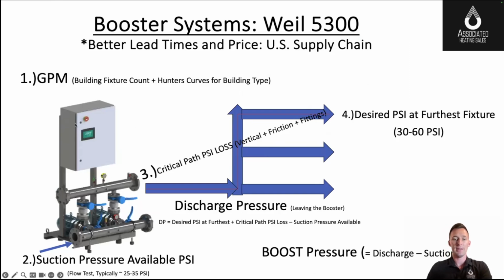So the idea here is that this panel, which is made at Weil Pump as well, has variable frequency drives to slowly turn a pump on or off to meet the demand at the building. So we're going to keep the discharge pressure of the discharge manifold the same, no matter what the demand is from the building. Designing these, you have a certain amount of flow that you need, and that can be found through the fixture count that you're supplying in the building. And Hunter's curves will tell you kind of what to design for.